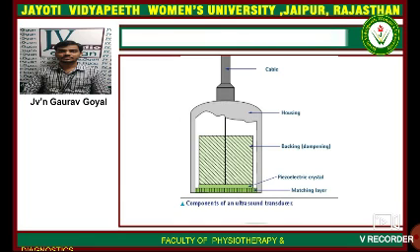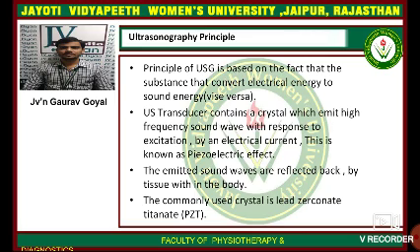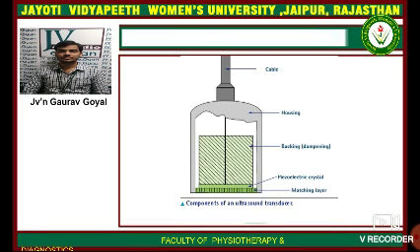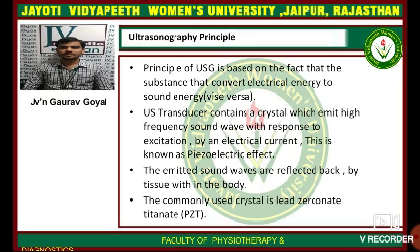It shows the backing damping block, and at the top of the transducer it has a piezoelectric crystal and the matching layer. The transducer has these components: a cable, housing, damping block, piezoelectric crystal, which is made up of lead zirconate titanate, PZT, and the matching layer.